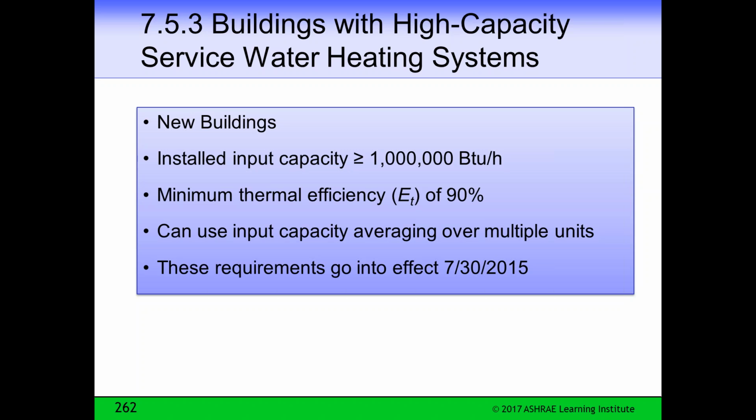Condensing boilers. Now we've said for many years in the committee that we would never, this is the minimum efficiency standard for all buildings built, and is a minimum efficiency standard. We thought we would never require condensing boilers. It just didn't seem logical. But there are so many condensing boilers being installed in practice today that we believe that even as a minimum standard, especially if you have a large requirement, we can require condensing boilers under those conditions. Again, these are fairly prominent now in the industry.